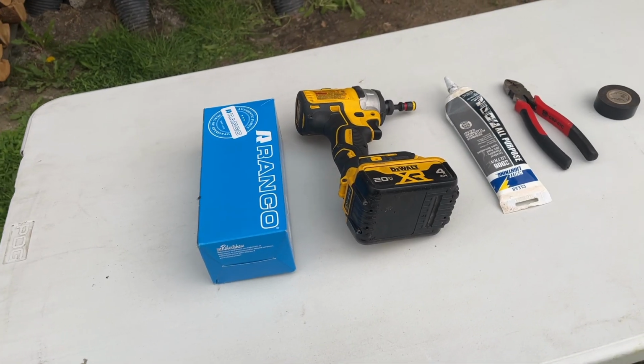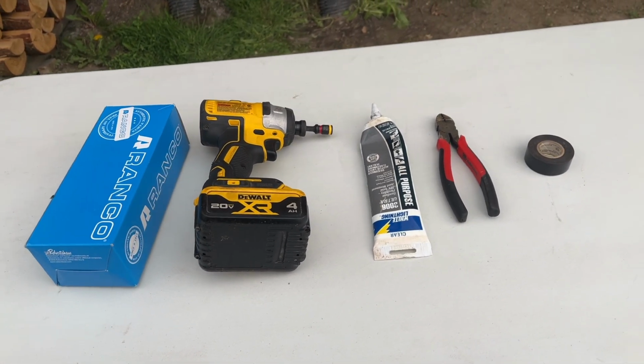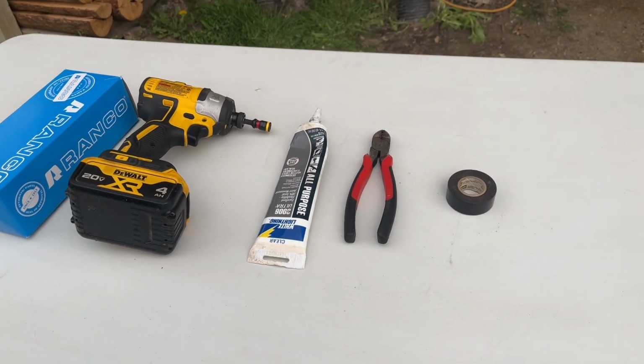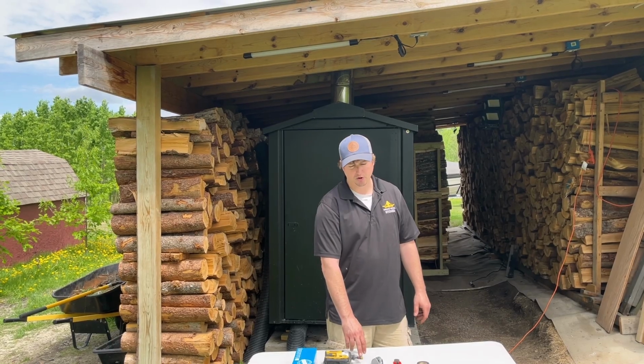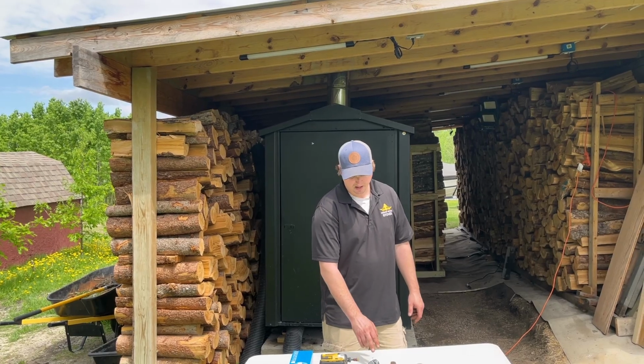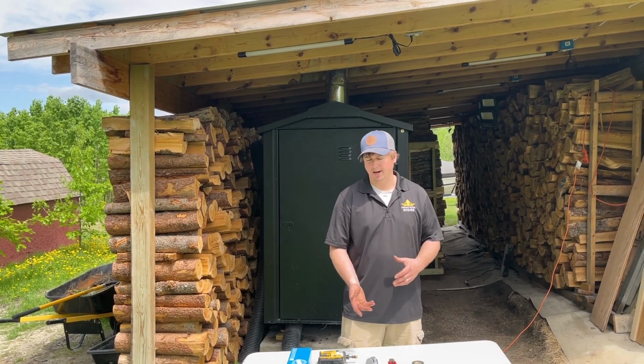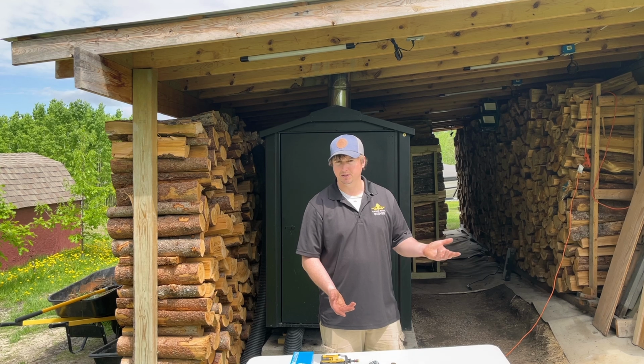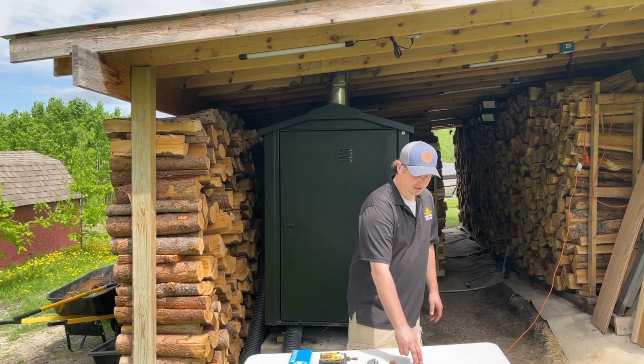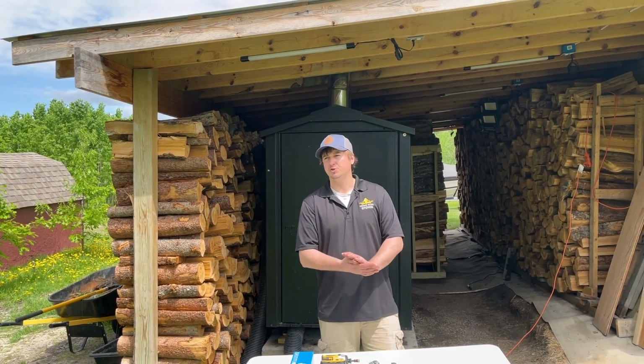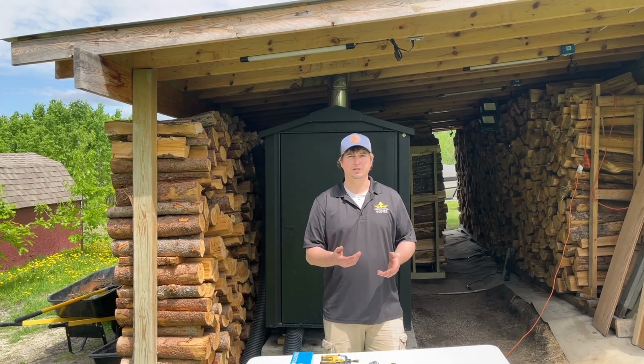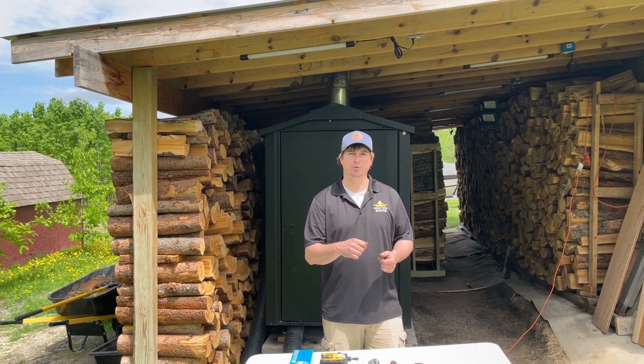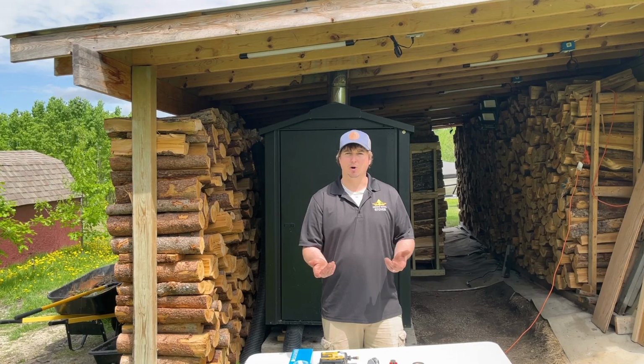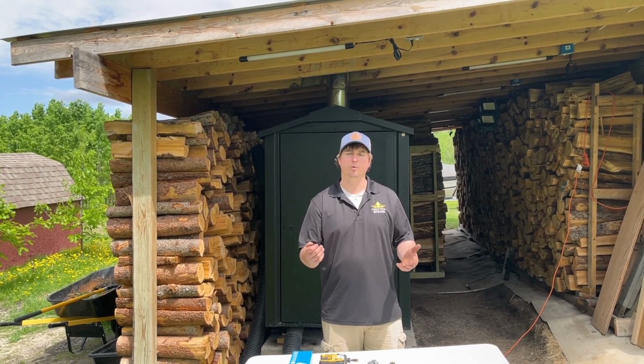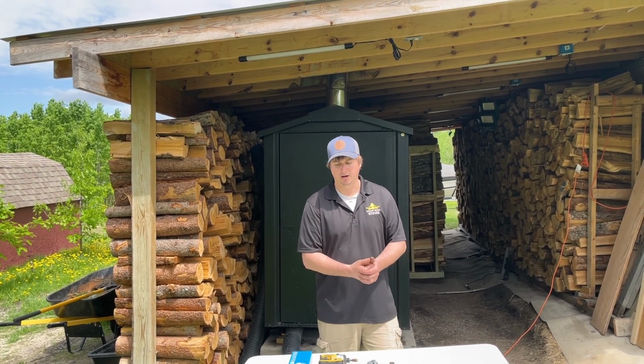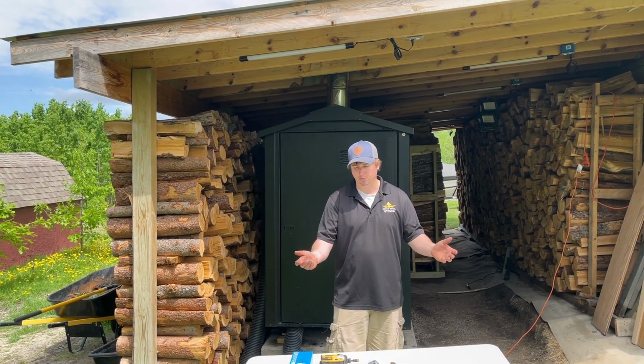Some of the tools you're going to want to have: an impact, or you can use a wrench or a socket drive, but you'll want a 1/4 inch bit and a 5/16 bit. I've got some silicone, either regular clear silicone or a high temp silicone. I've got some snips and some electrical tape. In some cases you may want a little grease or dish soap to help insert the probe into the thermal well, and maybe a small screwdriver to clean the thermal well out before installing the probe. That should be it as far as what we need.